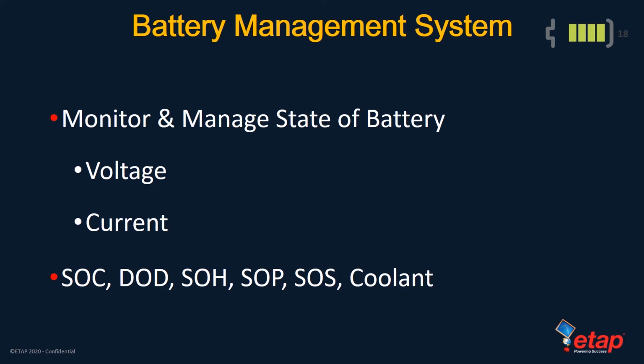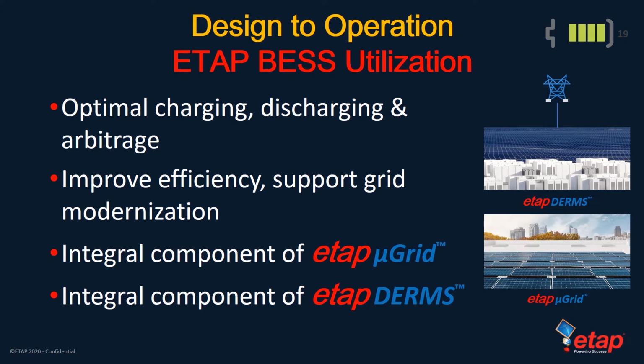It can also monitor state of power or SOP, the amount of power that is available for a defined time interval given the current power usage, temperature, and other conditions. Also, state of safety, aptly known as SOS, as well as coolant flow for air or fluid cooled batteries. In ETAP, battery energy storage systems are utilized all the way from design to operations. Now that we've seen some of the basic terminology of BESS, BMS, we can see that inside ETAP, the applications for battery energy storage system are obviously for optimal charging, discharging, and arbitrage calculations. And those computations can be used to improve efficiency and support grid modernization.